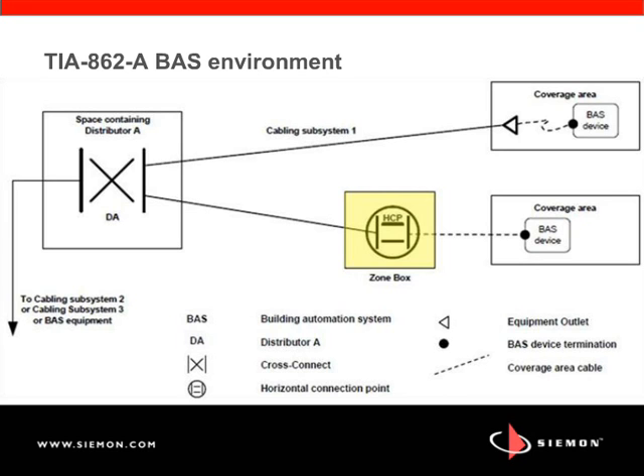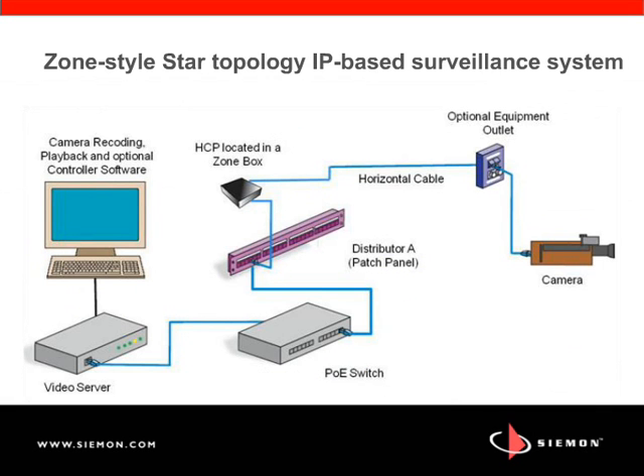But along with this flexibility, there are implications for cable selection. The Siemon Company recommends, for ease of deployment, ease of administration, supporting moves, adds, and changes, and labeling, that BAS systems be supported using a topology similar to what's shown in this screen. So we have a horizontal connection point that's located in the zone box, and we always have the optional equipment outlet in place, and that facilitates device connection. So here you see a zone-style star topology IP-based surveillance system. But there are implications that are associated with the cable selection here.